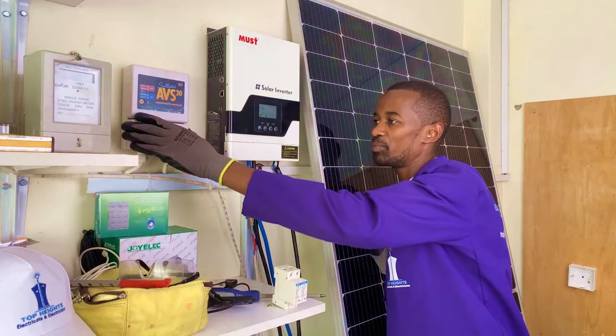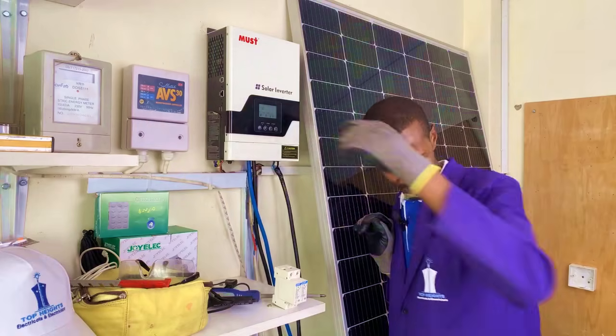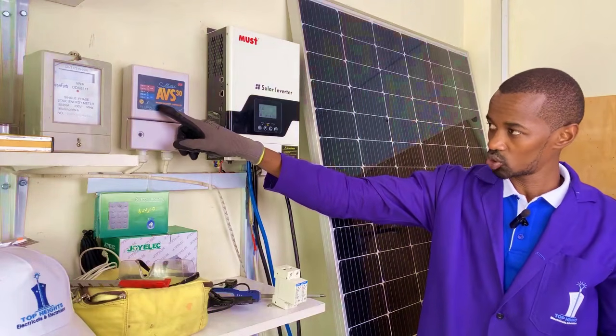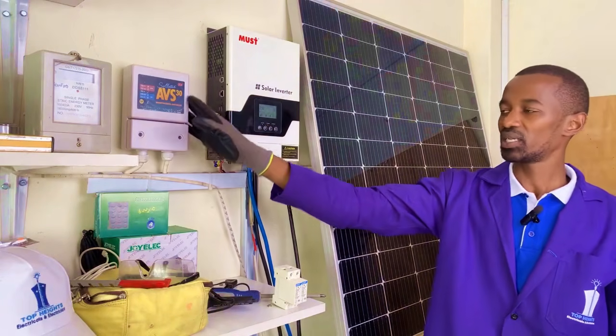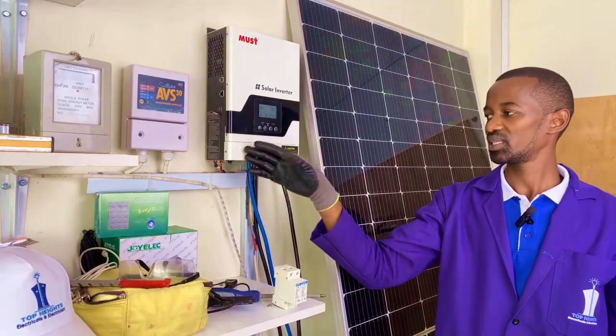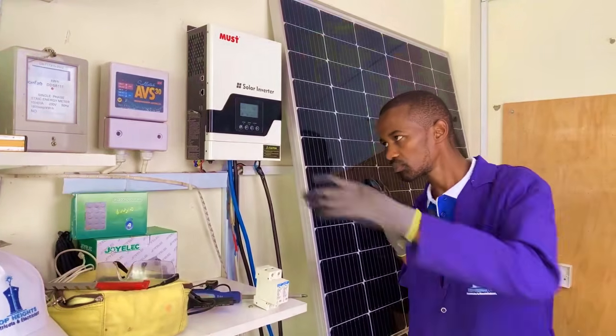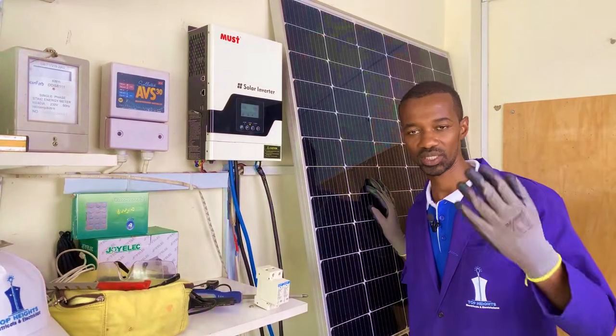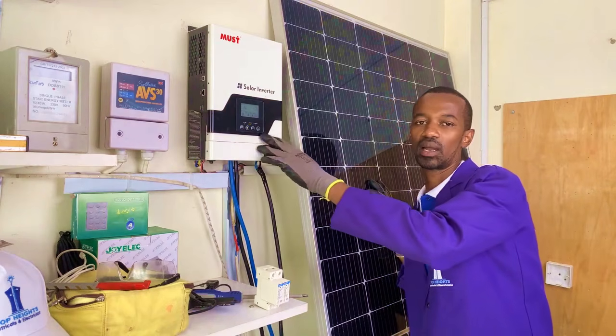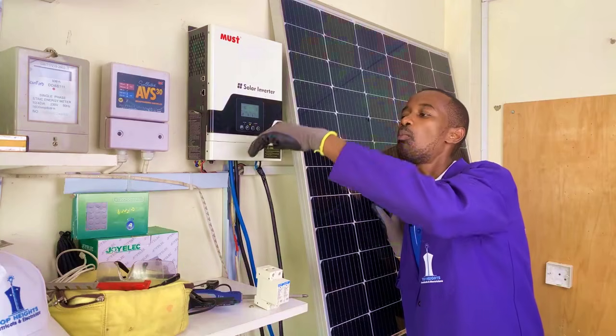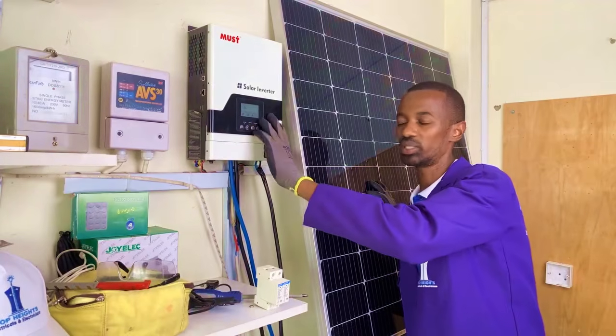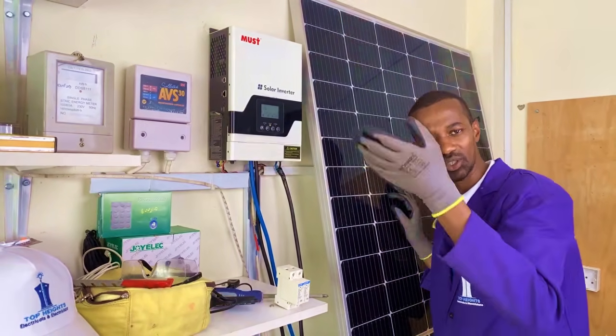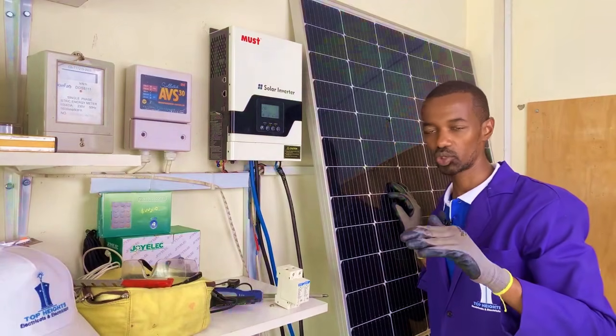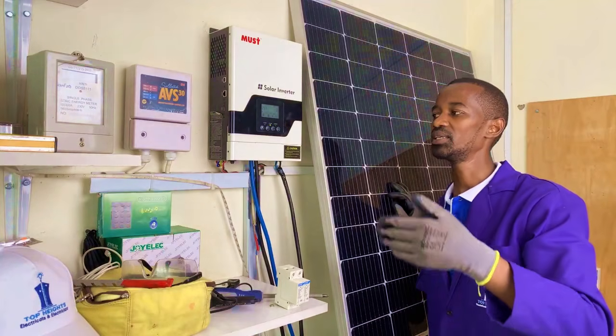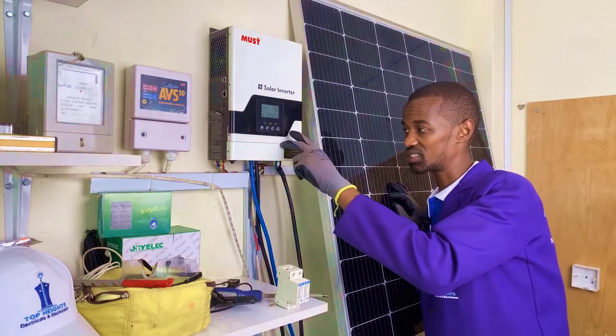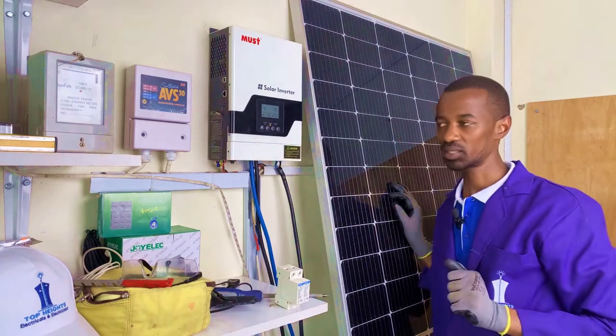Now another important aspect is this: what we refer to as an AVS, an automatic voltage switcher. It is simply a switch that monitors the incoming voltage, ensuring it is not less or more than required. Here in Kenya, this inverter has to be fed 230 volts AC. Anything way below that can cause the inverter to misbehave or get damaged, and anything well above 230 can also damage it. So this device monitors whether incoming voltage is below 220 volts AC or more than that, say 300 volts, which can be disastrous to this inverter. Those are the important devices required there.